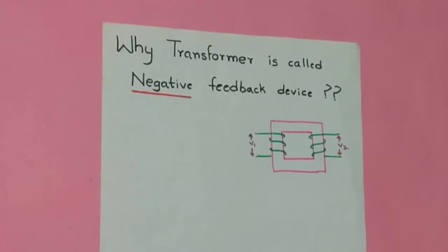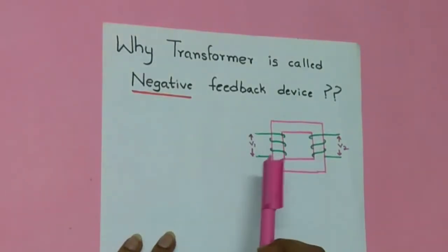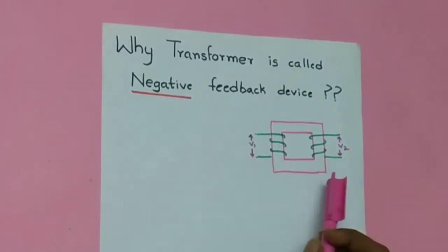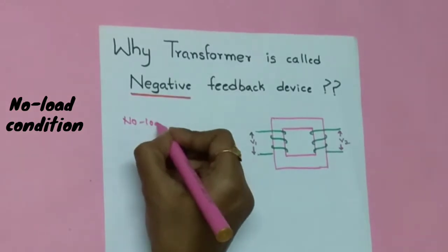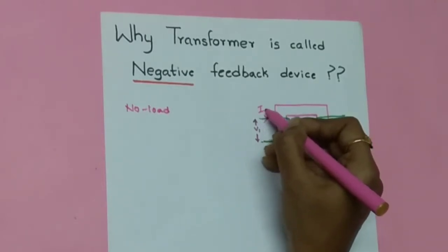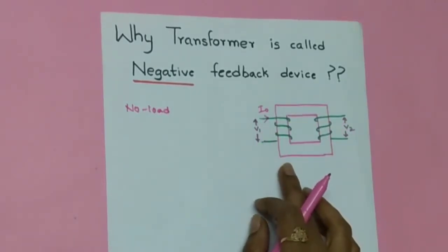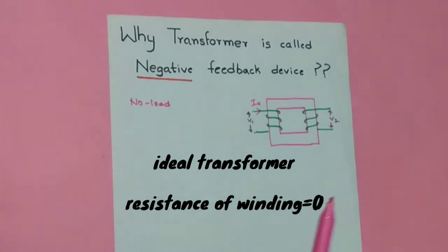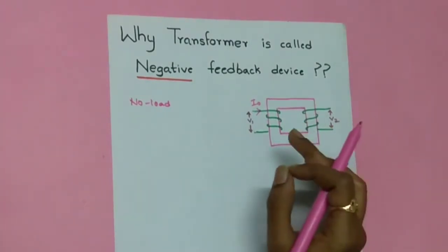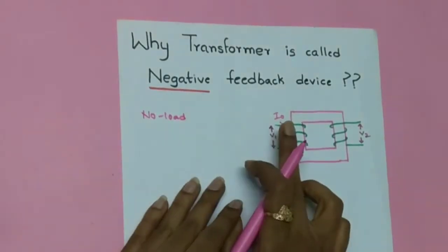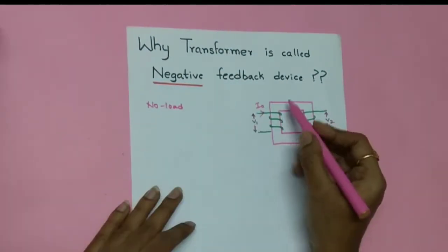Consider a two-winding transformer. I'm giving a sinusoidal voltage V1 at the primary side and not connecting any load at the secondary side — so right now considering it at no-load condition. Due to this potential difference, a current I0 flows in the primary winding. This is the no-load current. For an ideal transformer, the winding has zero resistance and is purely inductive, so I0 lags exactly 90 degrees behind V1.